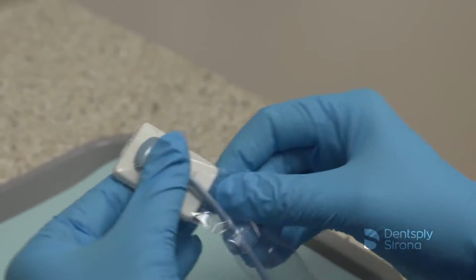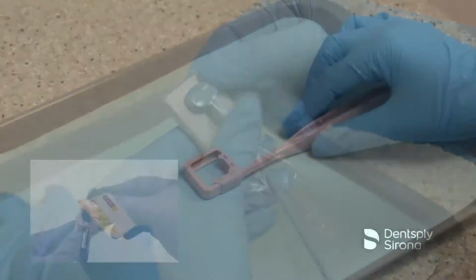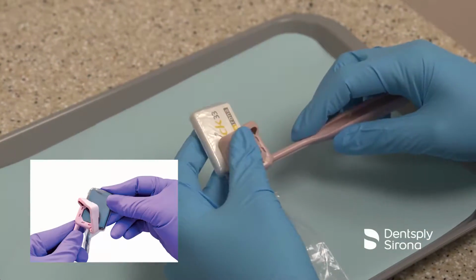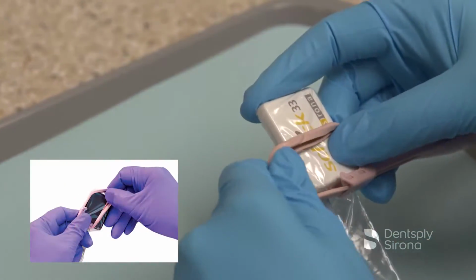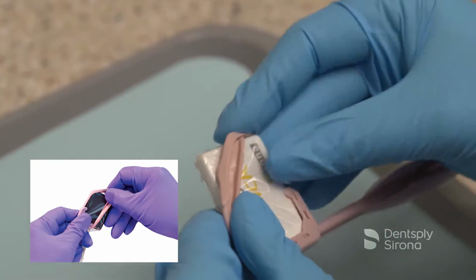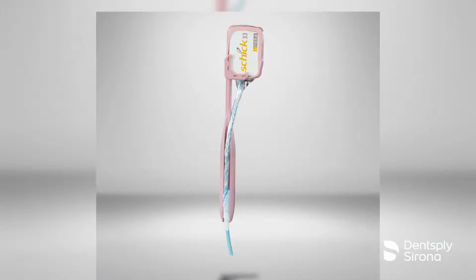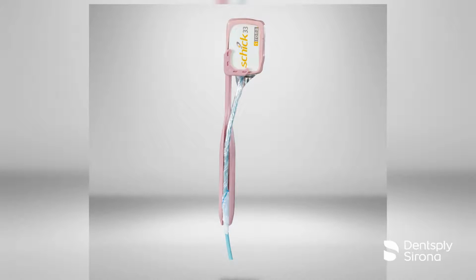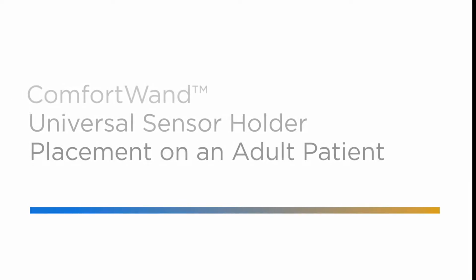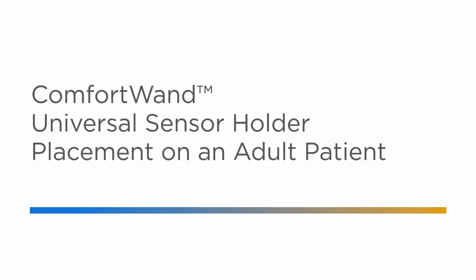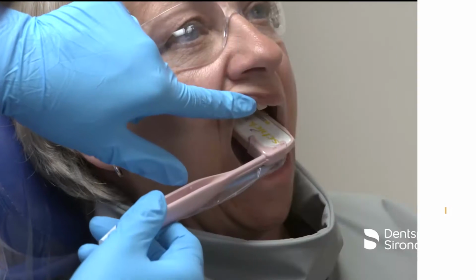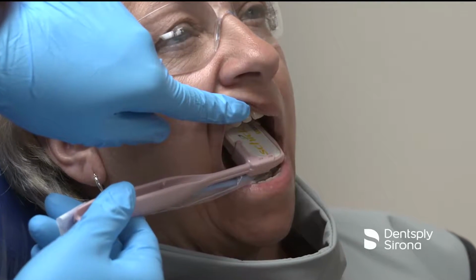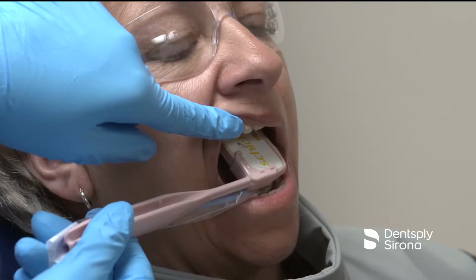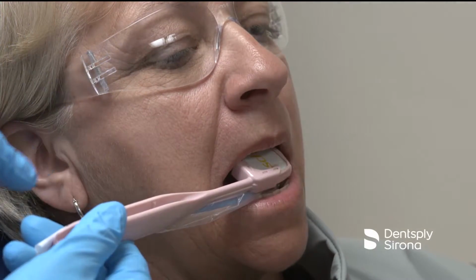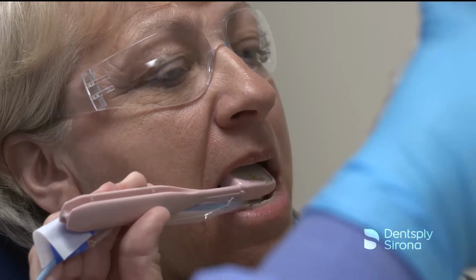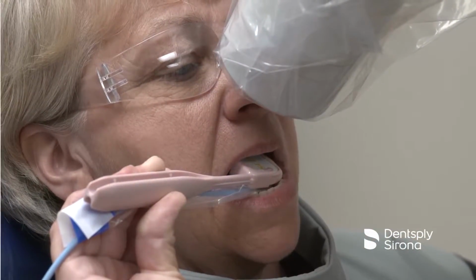Place a Rinn sensor cover over the digital sensor. Insert the corner of the sensor into the ComfortWand holder. Cover the edges of the sensor with the plastic strap to secure the sensor. Position the holder in the patient's mouth and have the patient hold the ComfortWand holder in place. Align the PID and the image is ready for exposure.